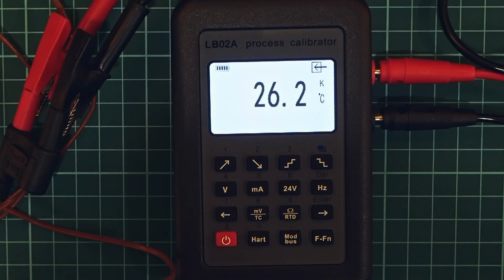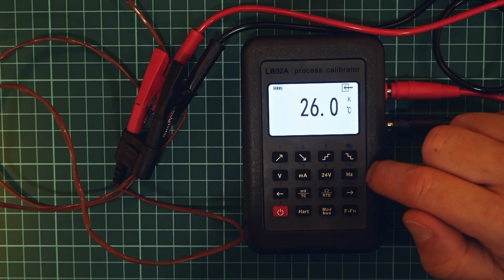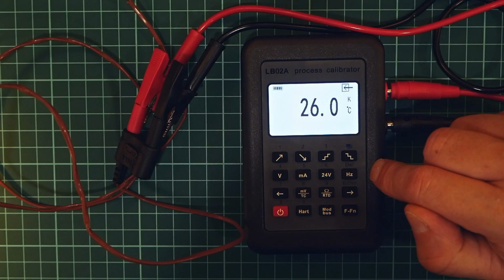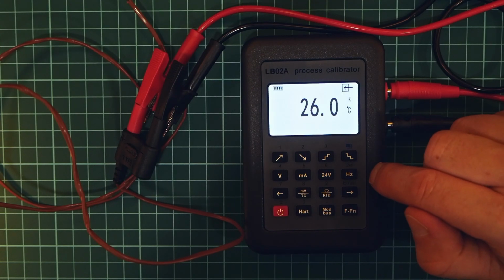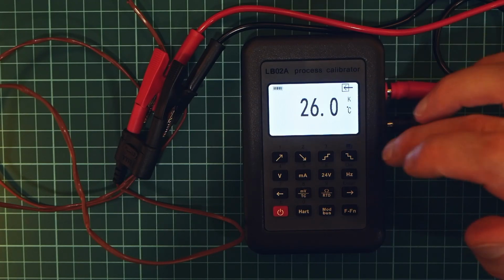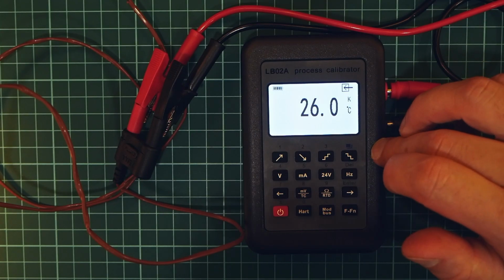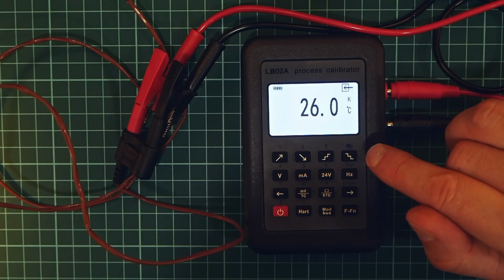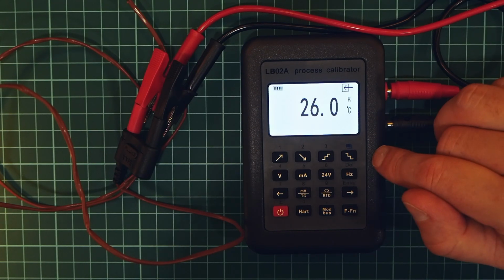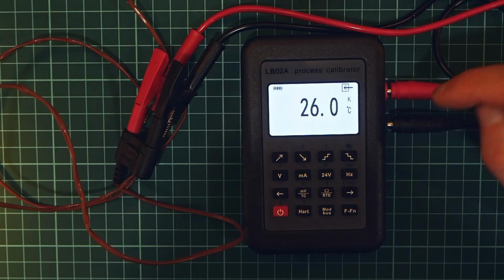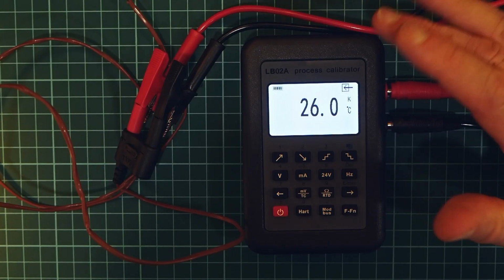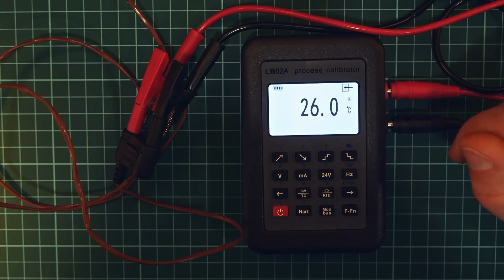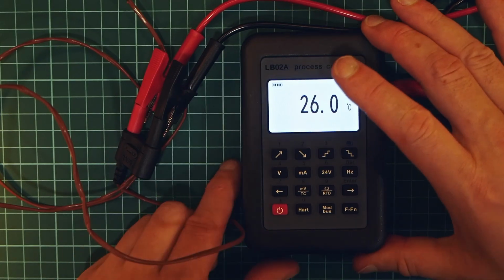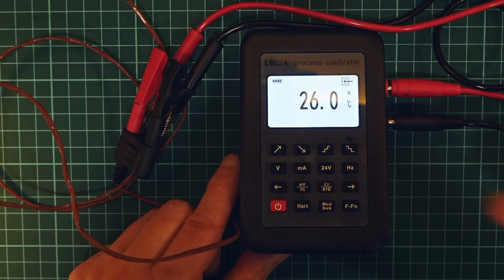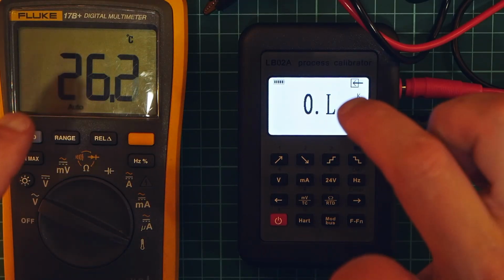Because when you are measuring thermocouples, basically, it has inside its own thermocouple. And when this device is basically powered on, the temperature rises inside this device. Components heat up, let's say capacitors, inductors, and so on. So it kind of drifts with the temperature. Don't expect it to be like a laboratory level device. The same value is not exactly the same from this to this.